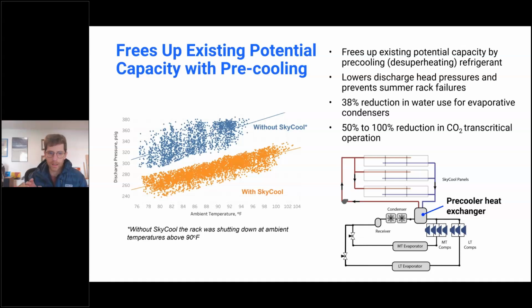Pre-cooling is essentially reducing the load on the condenser, but it's going to be more impactful to the energy use of the cooling system when the existing condenser is underperforming or it's at a limit where it's no longer able to reject enough heat from the refrigeration or cooling cycle. And so pre-cooling or desuperheating essentially is cooling the refrigerant after the hot discharge gas leaves the compressors. So it essentially allows the refrigerant to come into the condenser close to the saturation condensing pressure and temperature. In the case of underperforming condensers, essentially we're able to lower the discharge pressure for the system.